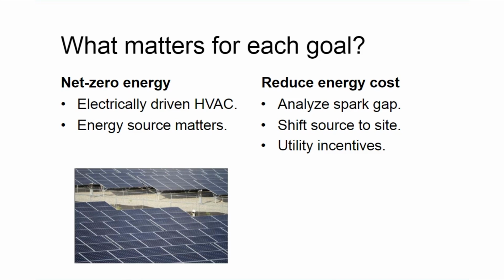So a net zero energy building goal, that's going to drive you towards wanting to consider more electrically driven HVAC equipment, because even the most efficient combustion-based equipment, condensing boilers, condensing hot water heaters, things like that, those are still a little less than 100% efficient. So even a typical straight electric resistance heating system is going to have 100% efficiency because you're really looking there, rather than cost, potentially at offsetting kWh for kWh or BTUs for BTUs. And so you really want to minimize what you're needing to offset in order to get to that net zero goal. So at that point, the energy source that you're using matters.